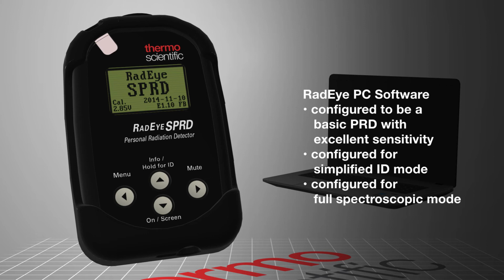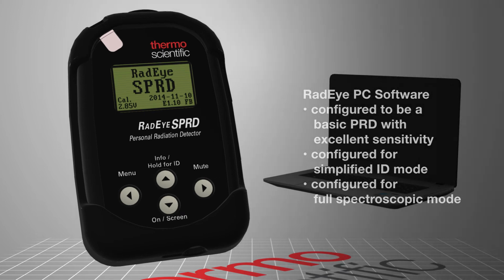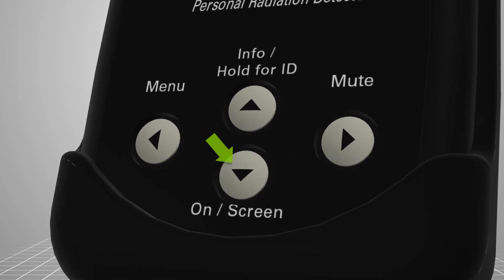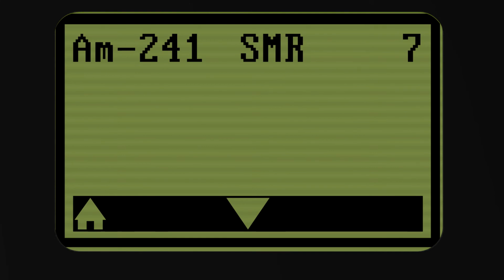If the RadEye SPRD is configured to show all of the spectroscopic details, the down arrow is used to scroll through a number of nuclide detail screens. This screen displays the nuclide that was identified, its class, special nuclear material, or SNM, and the confidence in its accuracy on a scale of 1 to 10.